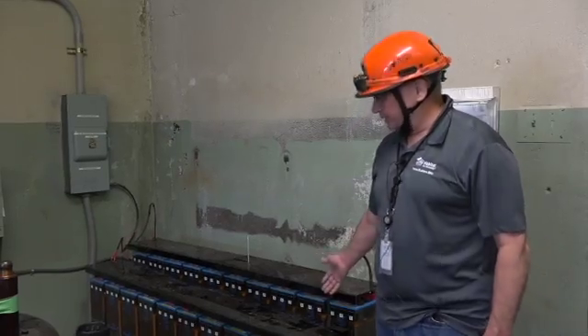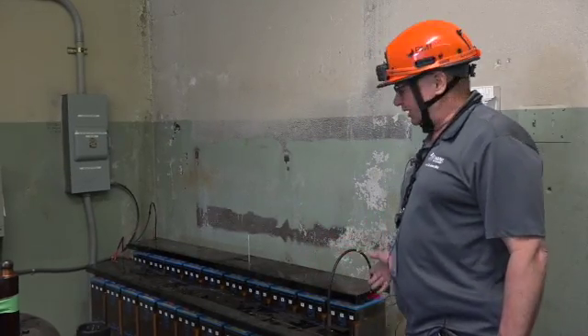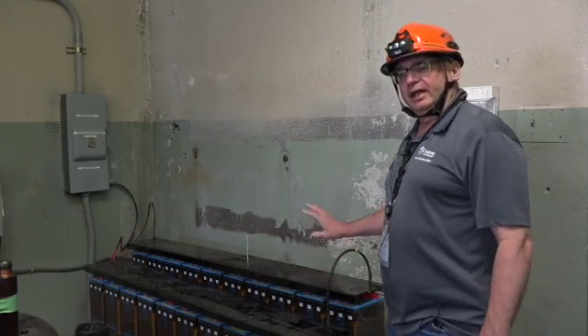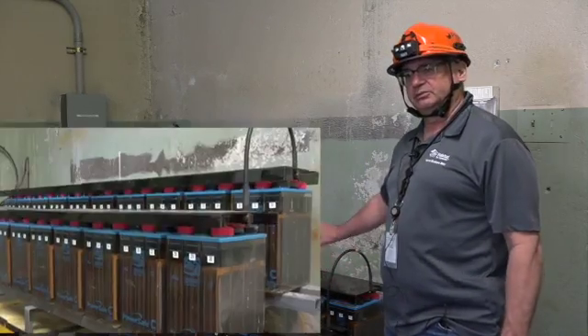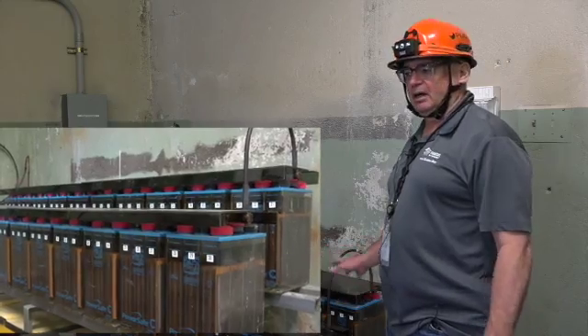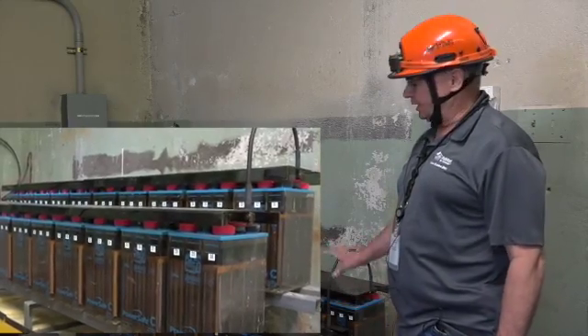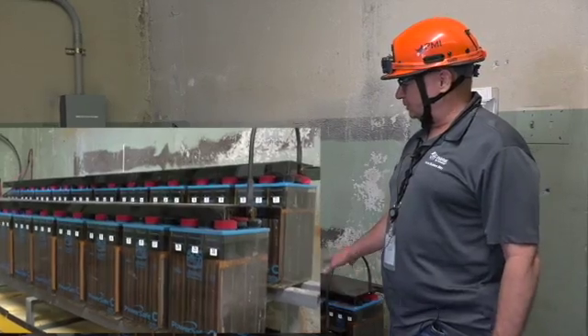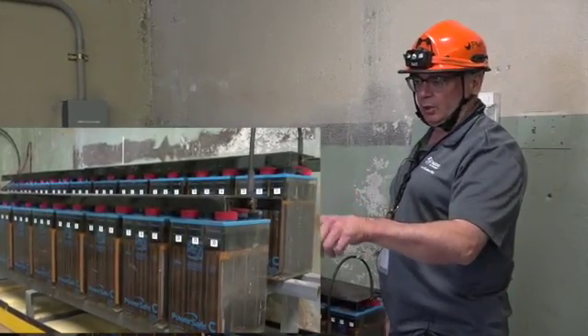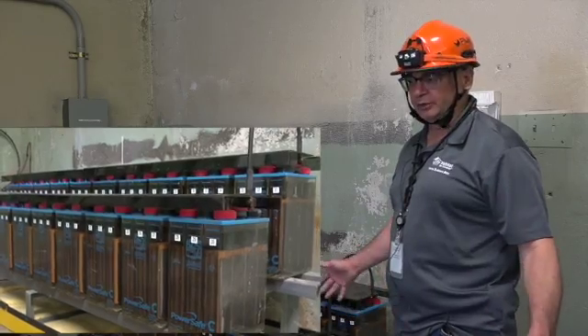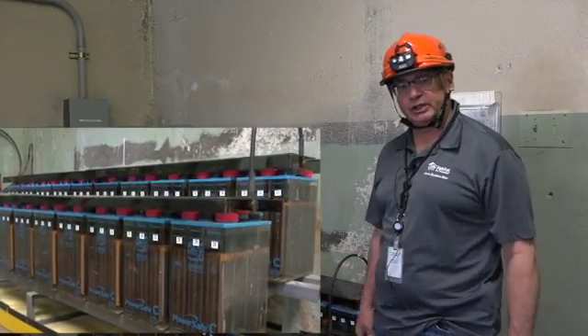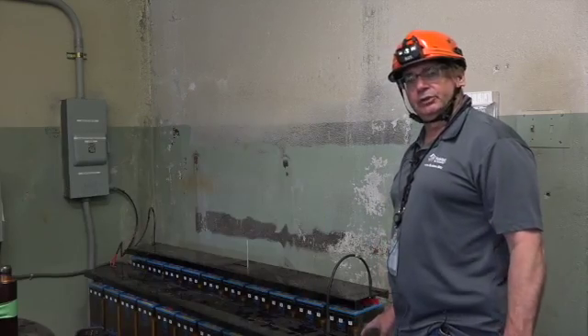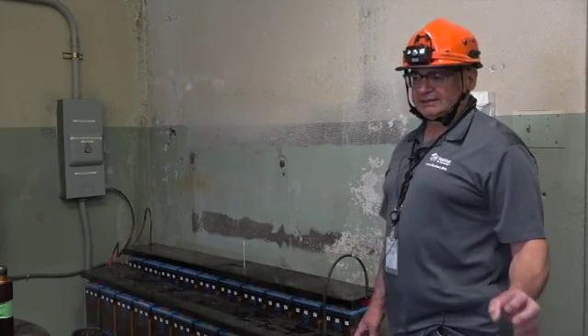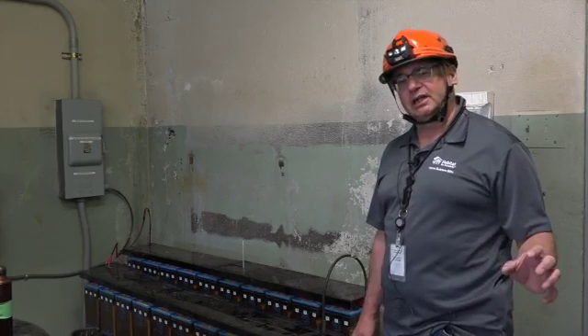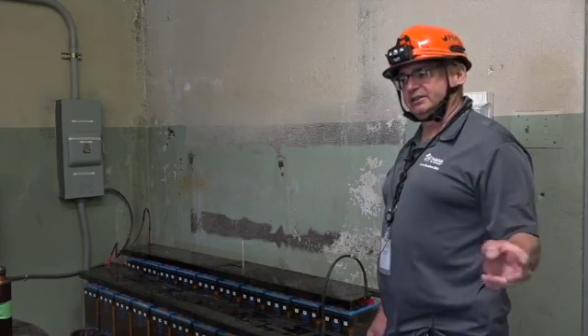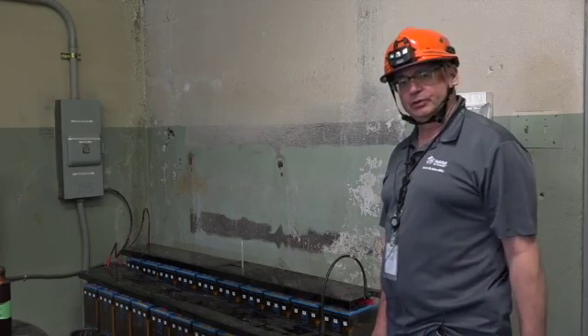This equipment here, they're lead acid batteries. It's called a battery rack. What these are for in a substation, all substations have them, they supply the DC power. It's 130 volts. They supply the DC power to be able to open and close the large 13.8 circuit breakers. There's also what they call trip relays, that sense the current on the electrical lines that then send the signal to the breaker to open up if there's a fault.